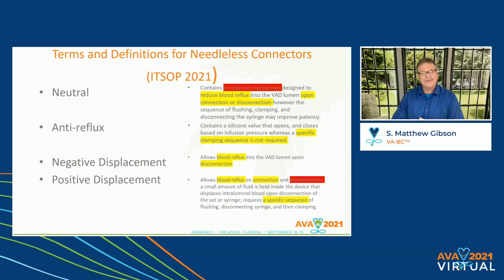So here are the current definitions of the different types of needleless connectors. Neutral contains an internal mechanism designed to reduce blood reflux upon connection and disconnection. We're going to have to talk about this a little bit more, but currently this is how it's defined. Anti-reflux is a connector that contains a silicone valve that opens and closes based on infusion pressure, and in the current standards they say these specifically have no clamping sequence required.